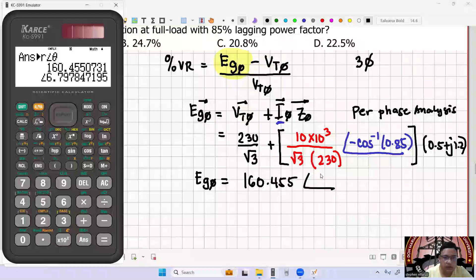So EG per phase equals 230 over square root of 3, plus 10 kilo over square root of 3 times 230, at angle negative arc cosine of 0.85, multiplied by 0.5 plus j1.2. Converting to polar form, this equals 160.455 at angle 6.79, or about 6.8 degrees.